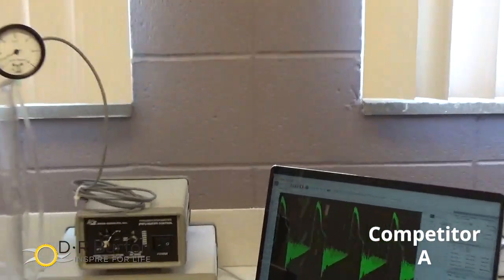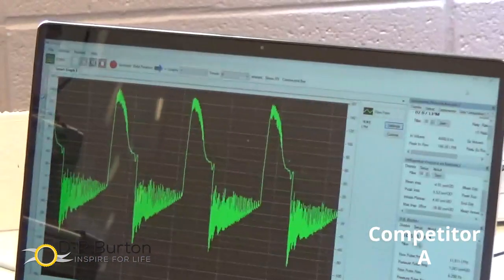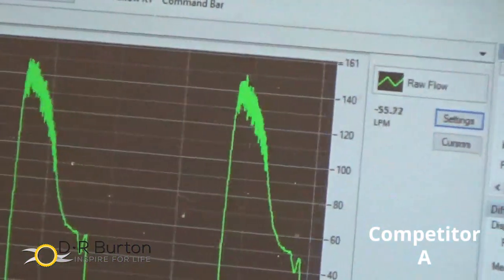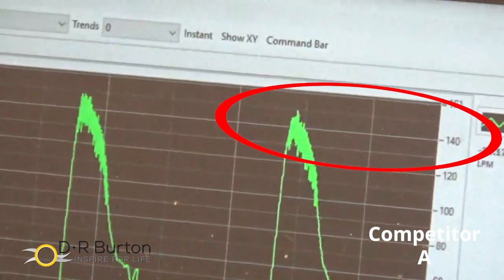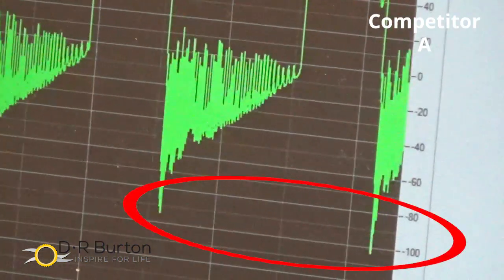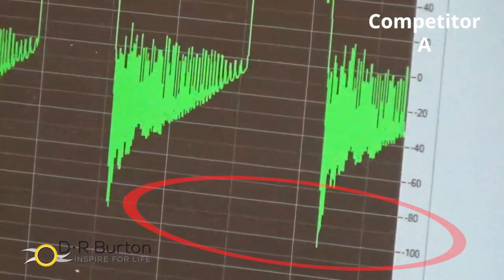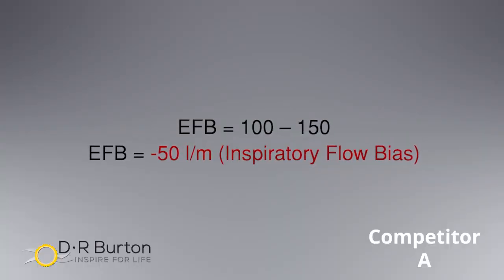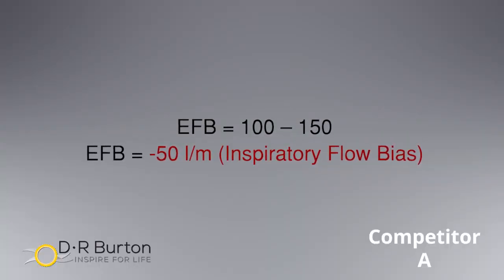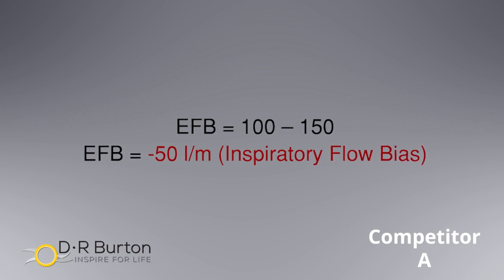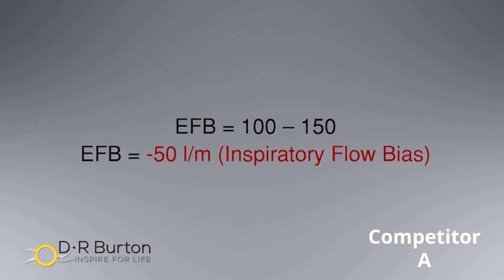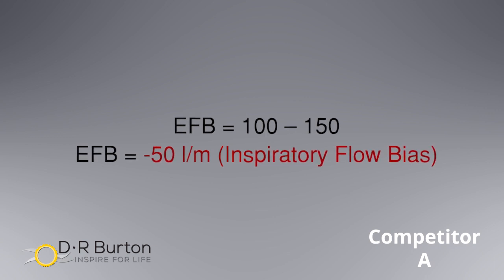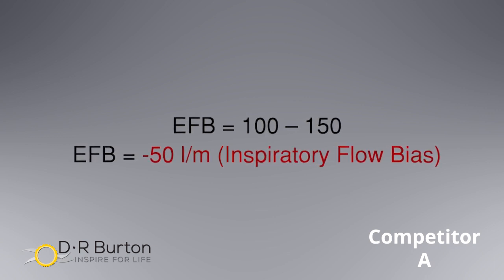Next, we compare the flow loops with a competitive OPEP device. As we zoom in on the flows, notice that the peak inspiratory flow is about 150 liters per minute, and the peak expiratory flow is 100 liters per minute. With a peak expiratory flow of 100 and peak inspiratory flow of 150 liters per minute, we have a negative expiratory flow bias — in this case, an inspiratory flow bias that would move secretions caudad, toward the periphery of the lung.